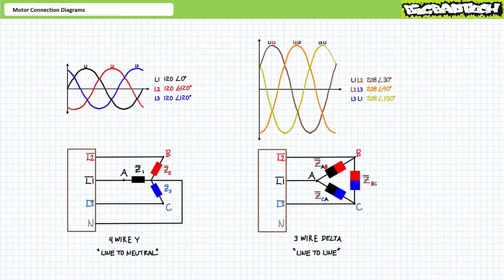It should be noted that all entries in a motor nameplate, unless explicitly stated otherwise, assume the higher line-to-line voltage, regardless of whether that motor is configured in Y or delta fashion. All entries in a motor nameplate assume the higher line-to-line voltage, regardless of whether that motor is configured in Y or delta fashion.